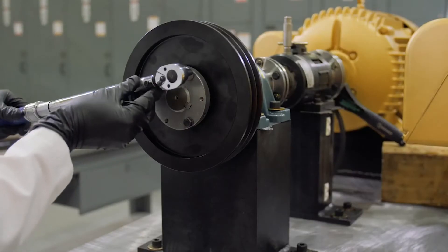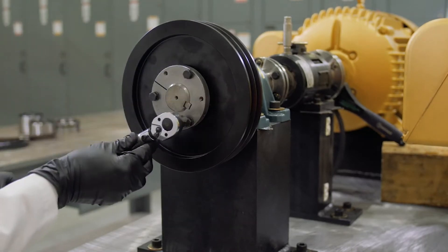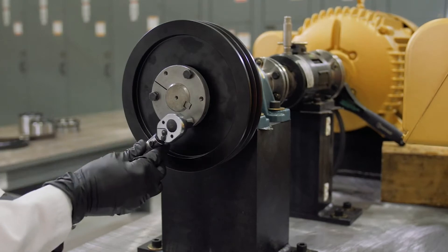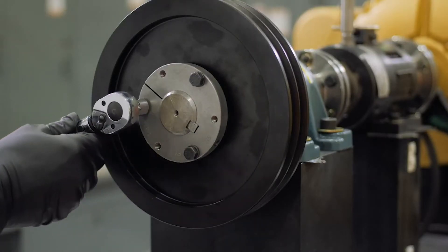Tighten bolts alternately and evenly in a star pattern to the torque value shown in the instruction manual with a calibrated torque wrench. Over-torquing can result in damage to the hub or bushing.